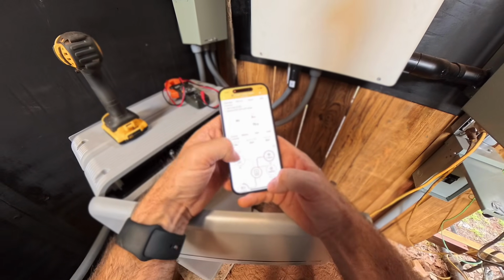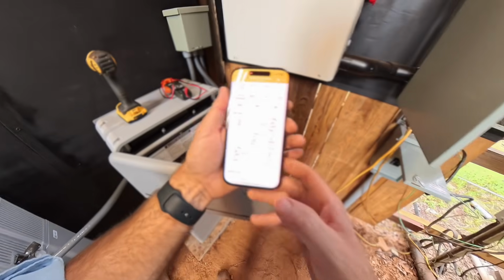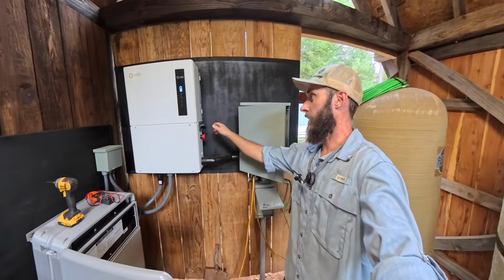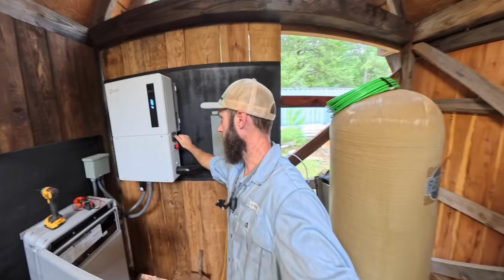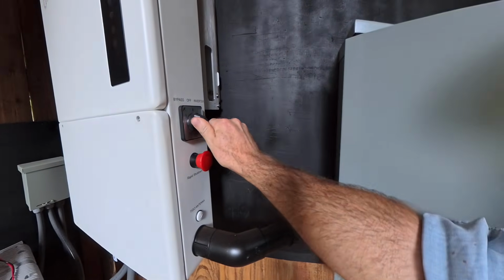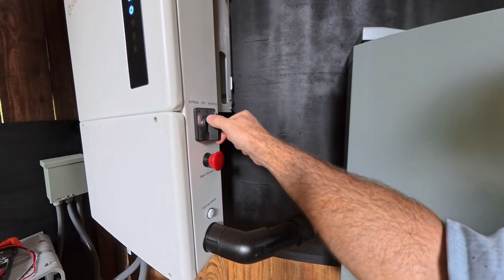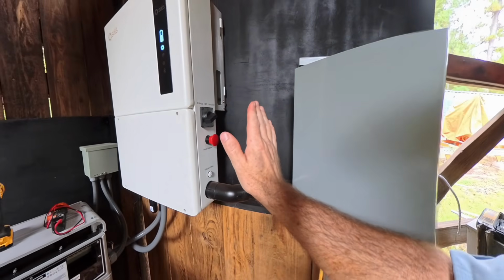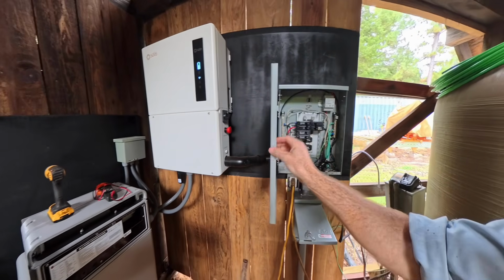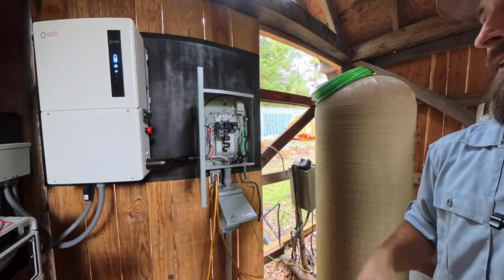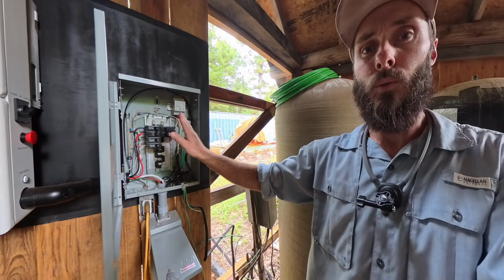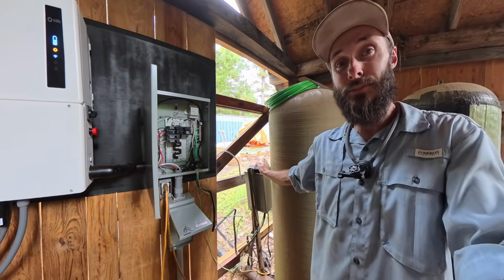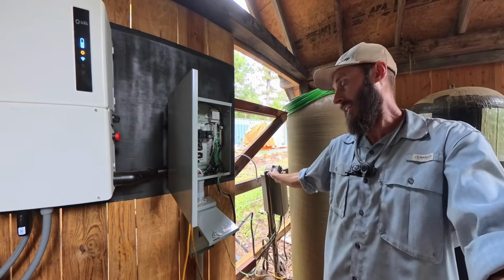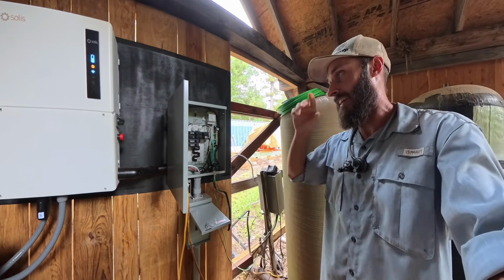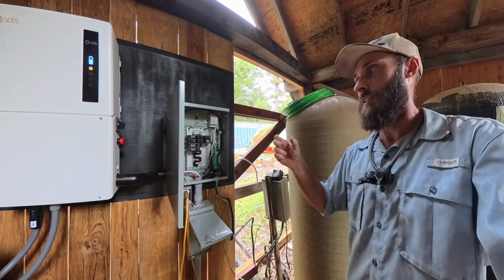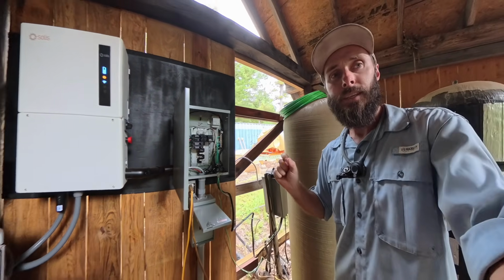I want to look here. Now we're going to flip this to off, and then flip it to inverter. It should take a minute, and then the power should be restored. Once we do that, I'm going to flip on the well pump. As you've seen many times before, it can't connect fully because it doesn't have enough voltage. I'm hoping this isn't going to be the case this time.